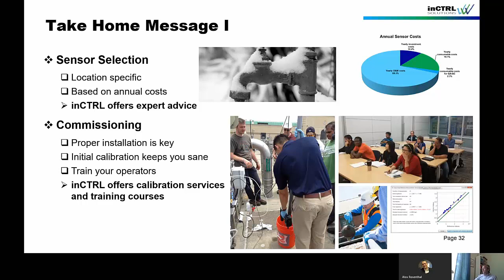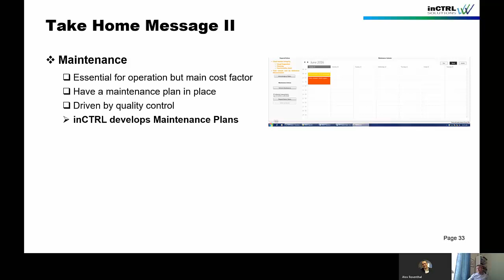In terms of maintenance, this is really the essential part for operation, but also the main cost factor. So you want to basically get to that compromise, that sweet spot where you limit the effort you spend on the sensor and maximize the quality of the sensors at the same time. That, in my opinion, is only possible if you have a maintenance plan in place. What we do is we drive that by quality control, so that's a special concept we have developed. InCTRL can help you in developing your own maintenance plan, or we can also provide this in form of software.